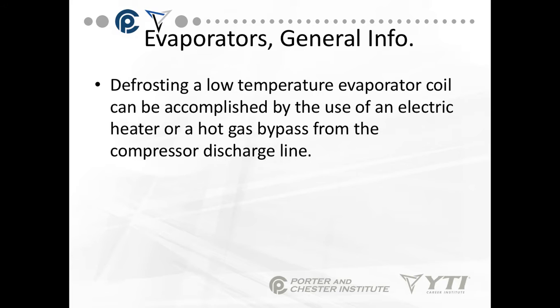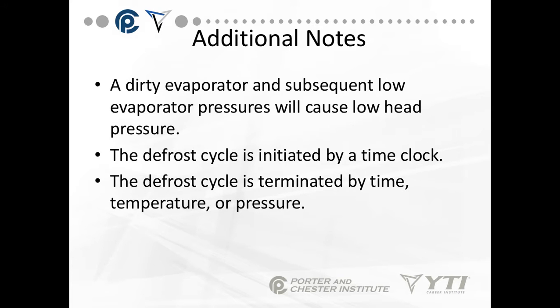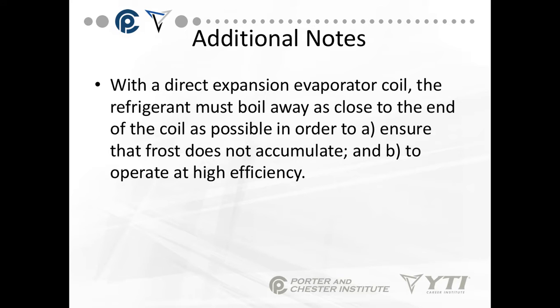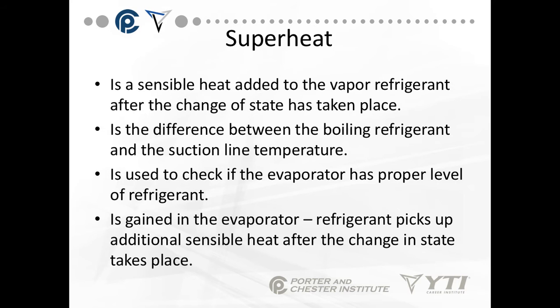Defrosting a low temperature evaporator coil can be accomplished by use of an electric heater or a hot gas bypass from the compressor discharge line. A dirty evaporator and subsequent low evaporator pressures will cause low head pressure — remember, head pressure is your high side pressure. The defrost cycle is initiated by a time clock and can be terminated by time, temperature, or pressure. With a direct expansion evaporator coil, the refrigerant must boil away as close to the end of the coil as possible to ensure frost doesn't accumulate and the evaporator continues to operate at high efficiency.